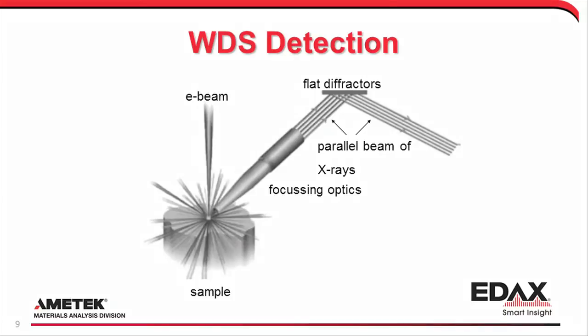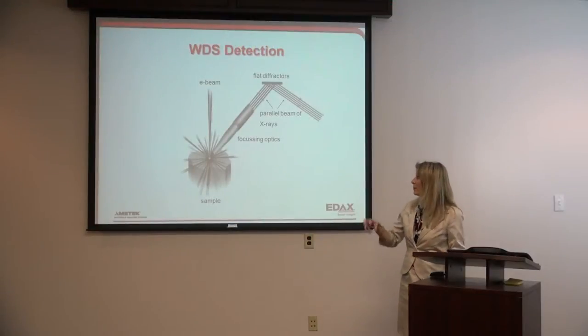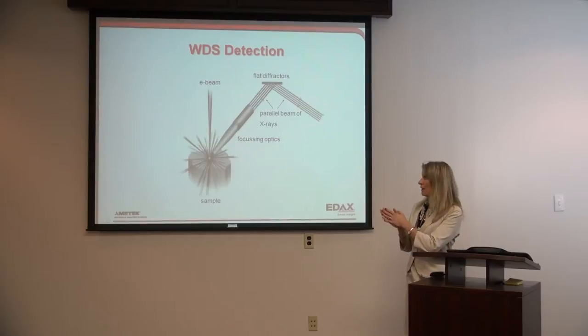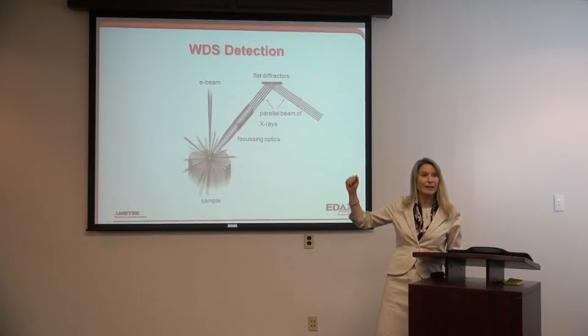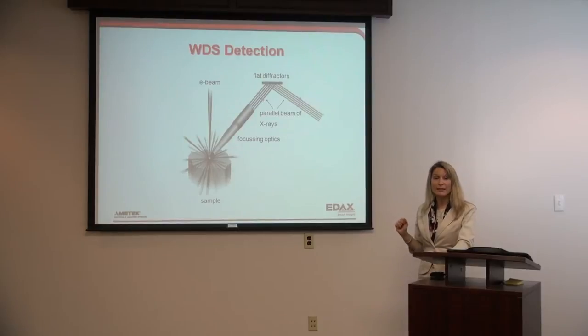Our focusing optics get in even closer than the other two technologies to maximize the collection and focus the X-rays through a parallel beam. The parallel beam is a technology that is relatively new in the WDS world. Traditional WDS spectrometers have been around for decades, but it's only been the last decade or two that we're figuring out how to focus X-rays. With the introduction of that technology, we've been able to apply that to WDS technology, and nowadays all new WDS detector designs are moving towards that new parallel beam because it gives us maximum collection efficiency.